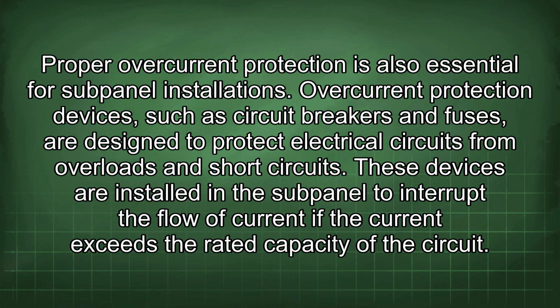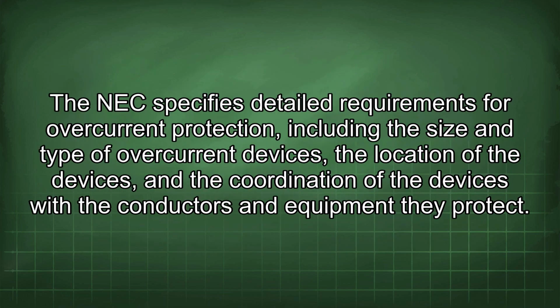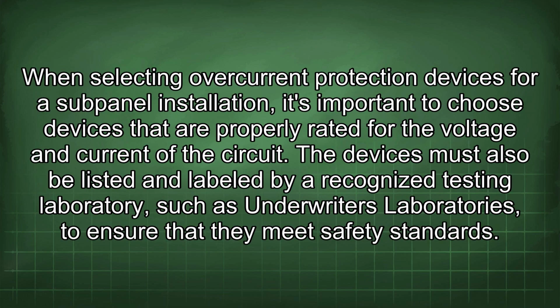These devices are installed in the subpanel to interrupt the flow of current if the current exceeds the rated capacity of the circuit. The NEC specifies detailed requirements for overcurrent protection, including the size and type of overcurrent devices, the location of the devices, and the coordination of the devices with the conductors and equipment they protect. When selecting overcurrent protection devices for a subpanel installation, it's important to choose devices that are properly rated for the voltage and current of the circuit.